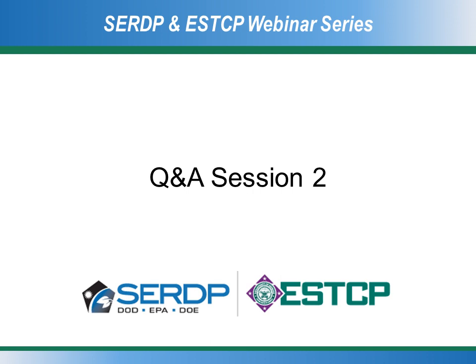I just want to point out that I think the technology that I described is an opportunity at lower cost to improve the monitoring, control and maintenance of your HVAC systems. And it can be done at lower cost than it might be done using purely physical sensors. Your current BMS supports monitoring and graphing trends over time for variables that are measured. The number and variety of flow rate sensors, though, is quite limited in systems generally. There are exceptions, though. And the BMS can provide alarms, which are most commonly used to alert operators when specific variables go outside of normal bounds.